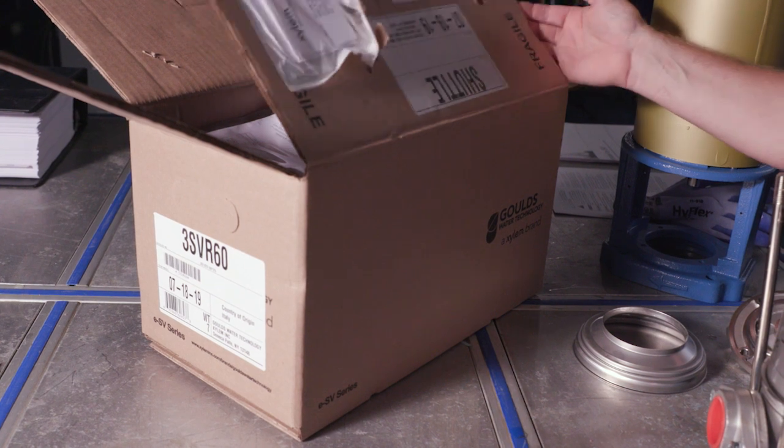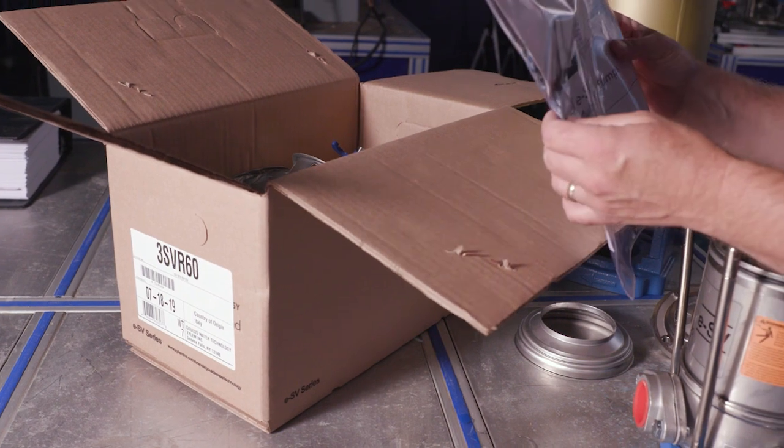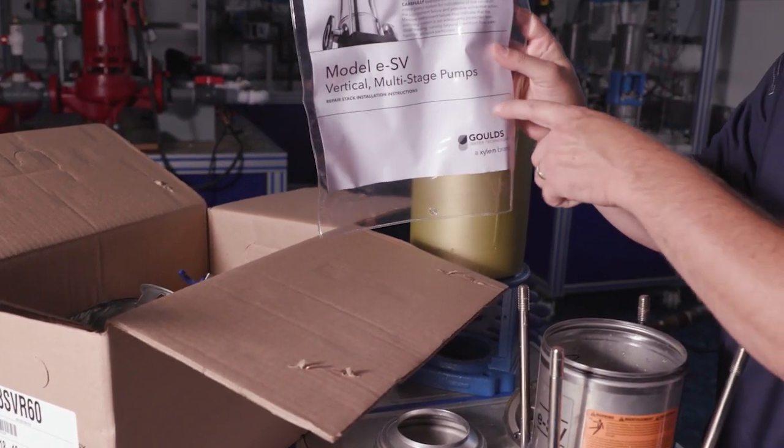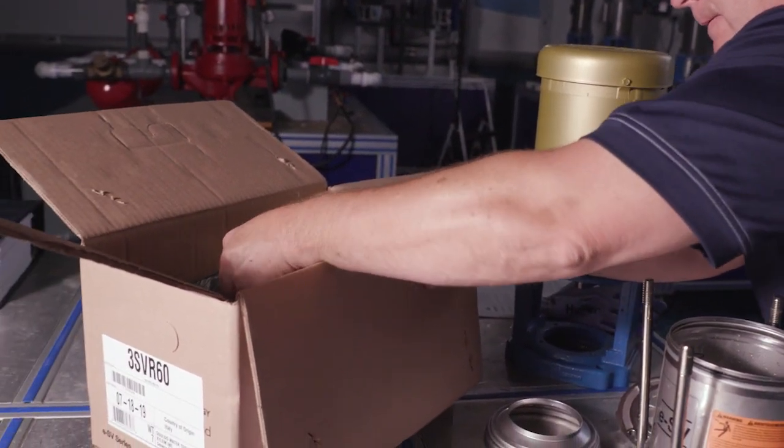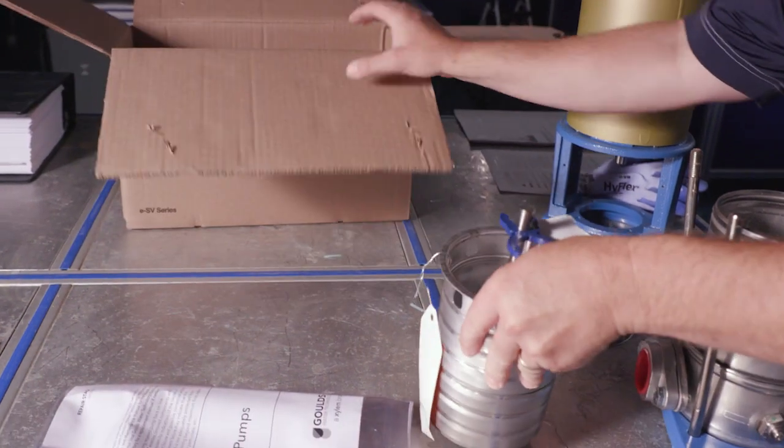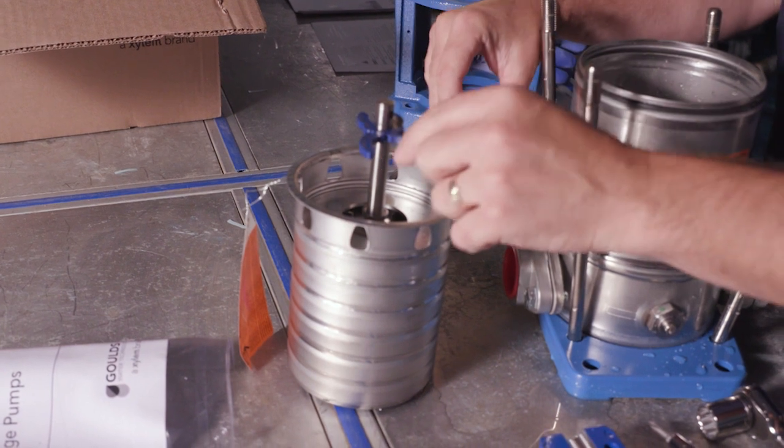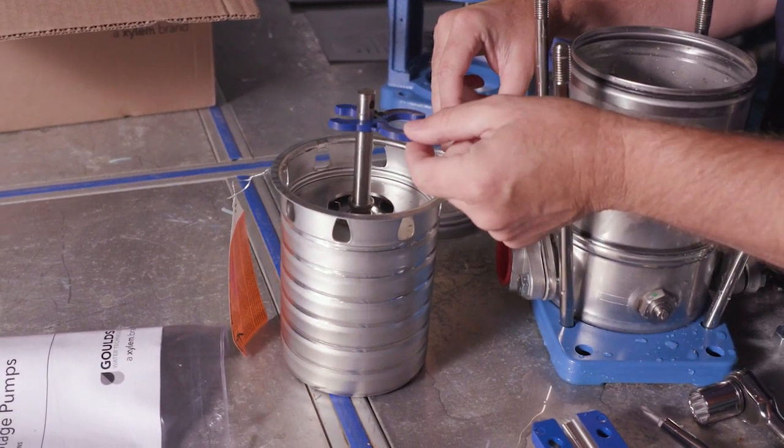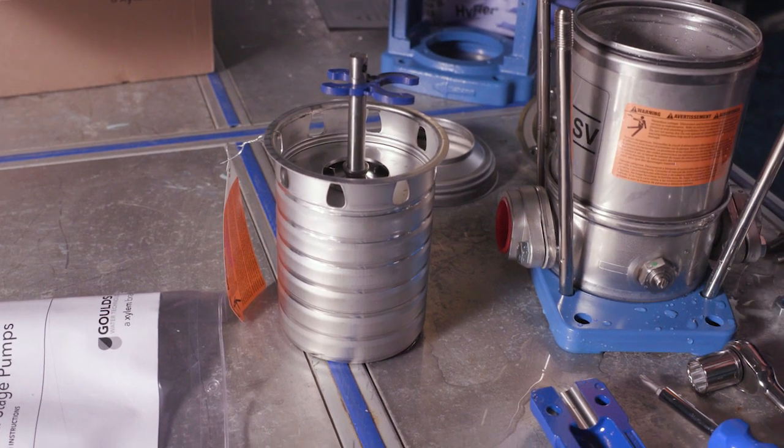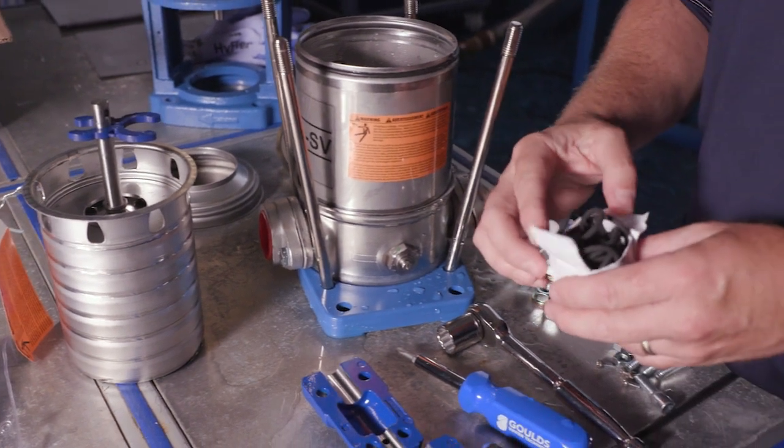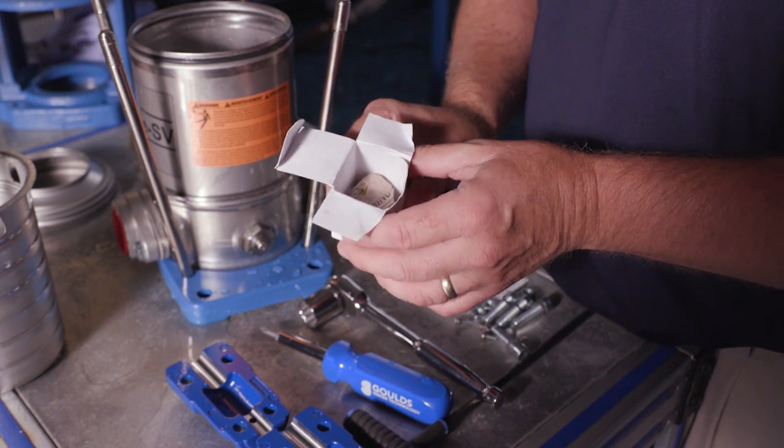Let's take a look at our repair stack, and this is a kit. The first thing that you get is the repair stack installation manual that we talked about earlier. You get the repair stack as we can see. You get the shim tool, which we're going to need that with the reinstall. And you also get this box here full of O-rings and a mechanical seal. Here's the mechanical seal; we'll put this in in a minute.